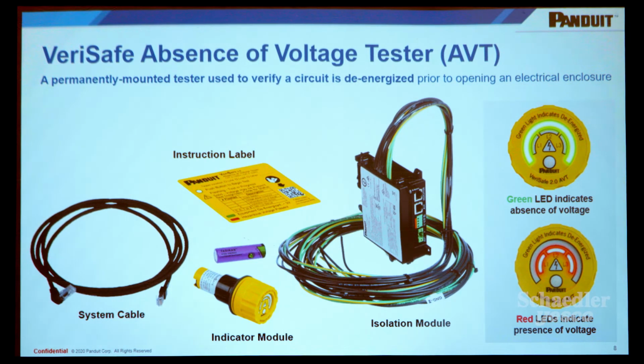And that's because the equipment has to also check that it's connected properly, so a wire hasn't just come disconnected because of vibration or something. So it does a positive connection test, and 2 wires to each phase and 2 wires to ground ensure that that happens. By the way, the system also doesn't bring any high voltage to the door. It's less than 5 volts going to the door, so you don't have any high voltages to worry about at the indicator module as well.